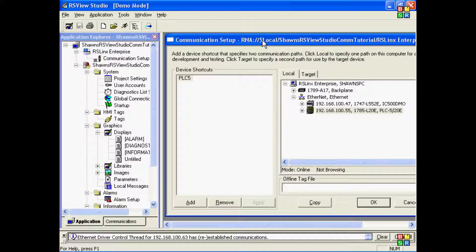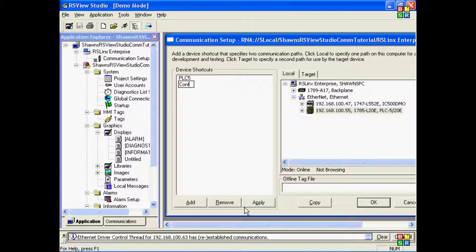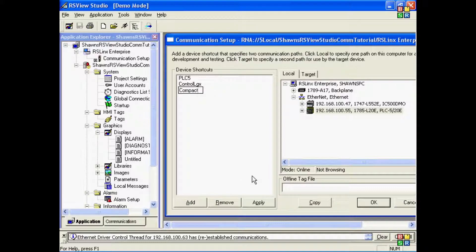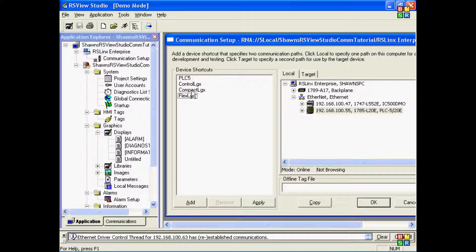In the communications setup window of RSLinx Enterprise, I'll now add in three separate shortcuts to point to three separate Logix-based processors. I'll add in a ControlLogix, I'll add in a CompactLogix, and I'll add in a FlexLogix. Now remember not to put any spaces or non-alphanumeric characters in your shortcut names.